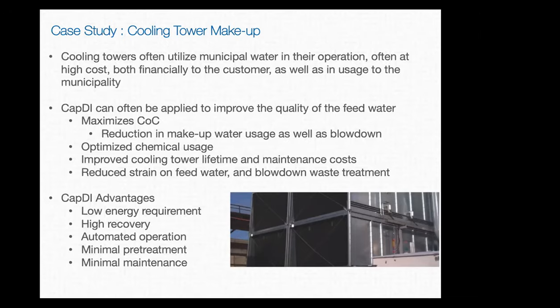By starting the water off with a higher quality, the chemical will stay in the cooling tower for longer. So not only are they minimizing the water that they're making up to the cooling tower, they're maximizing the efficiency of the chemical and minimizing the amount they need, because it's cycling and staying in the cooling tower for longer, which allows them to reduce the amount of blowdown. So we can improve the efficiency of those cooling towers, as well as reduce the makeup water and blowdown that they may need to treat.